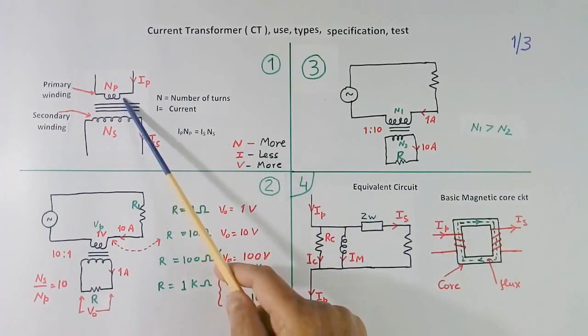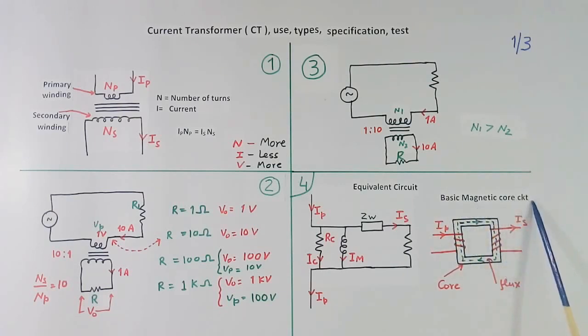This is equivalent circuit of the CT. And this is basic magnetic core circuit. This is core. And this is primary winding, this is secondary winding. This is primary current, secondary current. When current flows in this, some flux has to flow. Otherwise you will not get current here. This flux requires some magnetizing current. That is called IM. That I have shown here. And there will be loss in this core. That equivalent of that loss is shown here. Rc, resistance core. It is equivalent or current flowing IC, core current, core loss current.